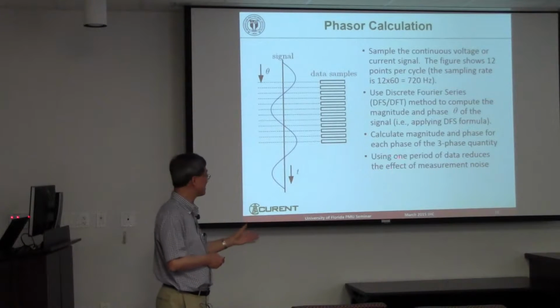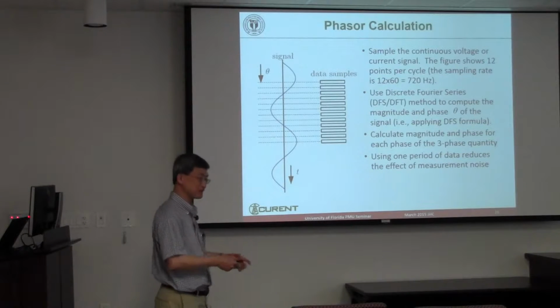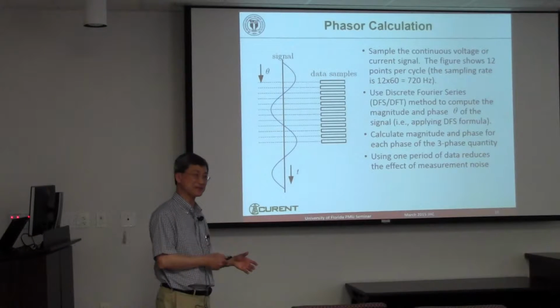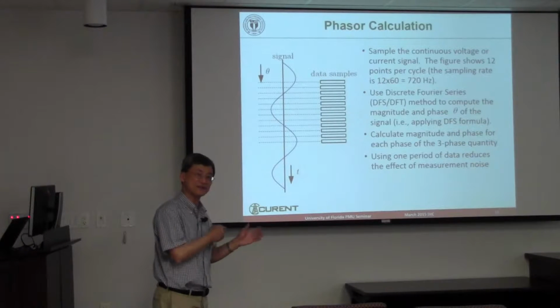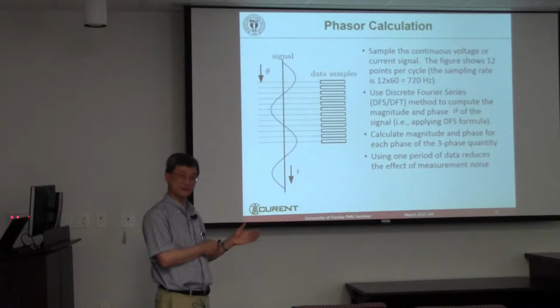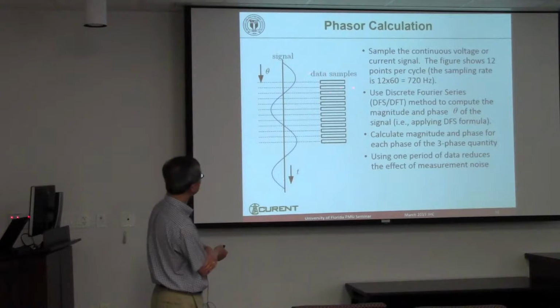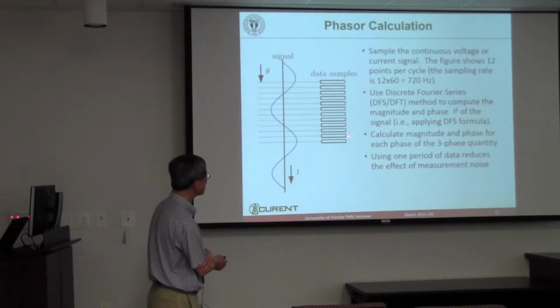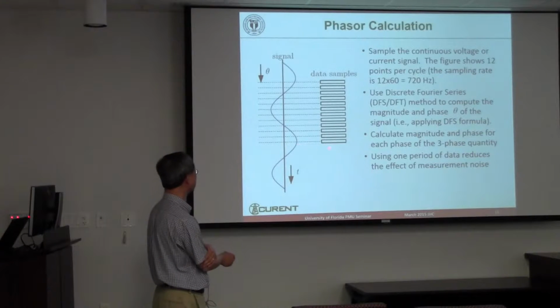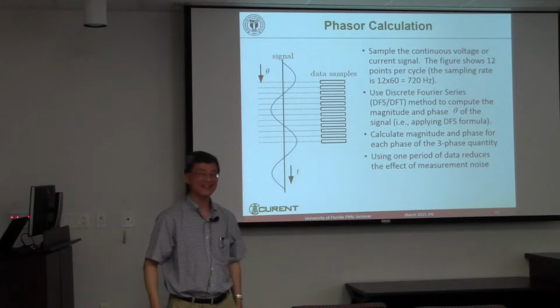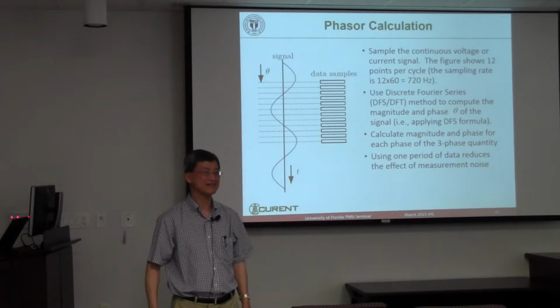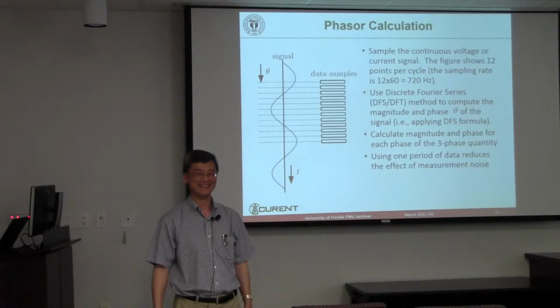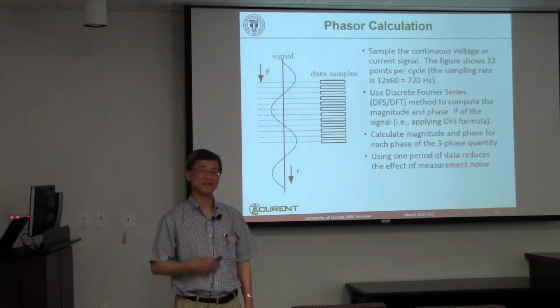So one of the things people were trying to do, because the microprocessor in those days was still expensive, was an iterative discrete Fourier transform. If you have a new data point here, you can drop this data point value, do a phase shift, and put in the new data point. And then General Electric found that something was screwy after a while. You know what happened? The phasor would not be accurate.